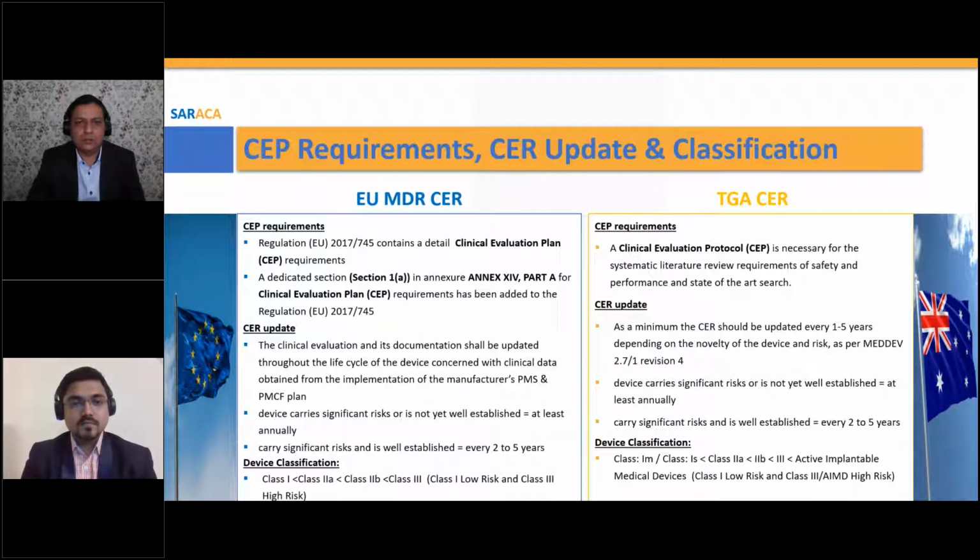For the CER update in the TGA, as a minimum, the CER should be updated every 1 to 5 years, depending upon the novelty of the device and risk, as per MedDev 2.7 revision 4. It's a little different in the EU, where the clinical evaluation and its documents shall be updated throughout the life cycle of the device with clinical data obtained from the manufacturer's post-market surveillance and PMCF plan.